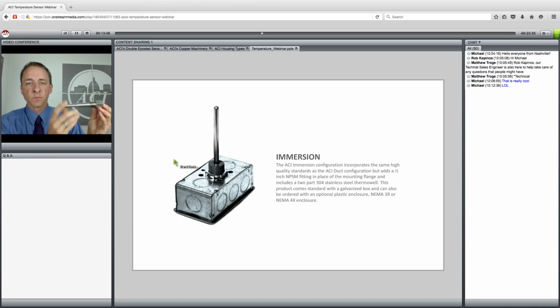So oftentimes someone will pull a sensor out of an existing well, measure it and say it's 6 inches long, and then call me and say, hey, Brand, I need a 6-inch immersion sensor, and we send them a sensor that's a little bit longer. So we measure it from below the thread of the well to the tip of the probe, the actual insertion length. So on our data sheet and on our ordering grid, when it says a 6-inch immersion sensor or 4-inch, that's from here to here.